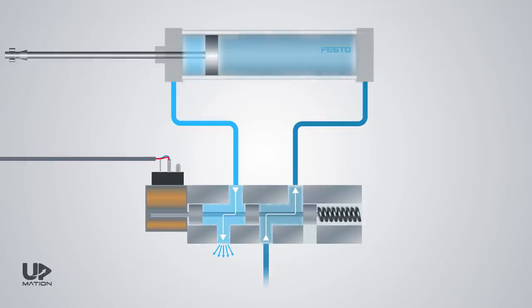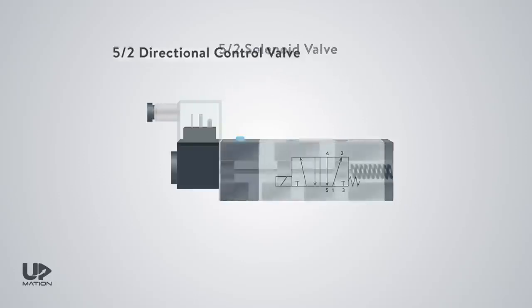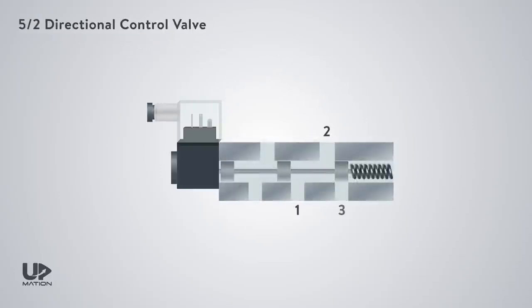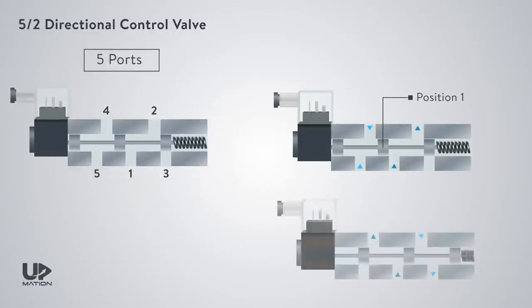Now it's time to learn how these valves are called and how to read their graphic symbols. This valve is known as a 5/2 solenoid valve or a 5/2 pneumatic directional control valve. The first digit is for the number of ports the valve has, and the second digit is for the number of states the spool can be in.